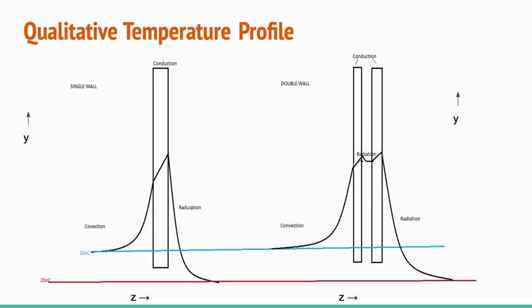When we use the double wall instead of the single wall, the heat in the form of radiation gets partially reflected from the second wall and sent back into the incubator. This reduces the heat loss to the surroundings through radiation.